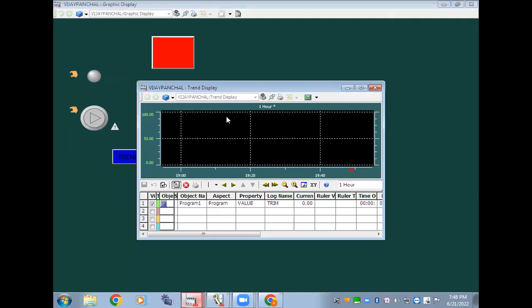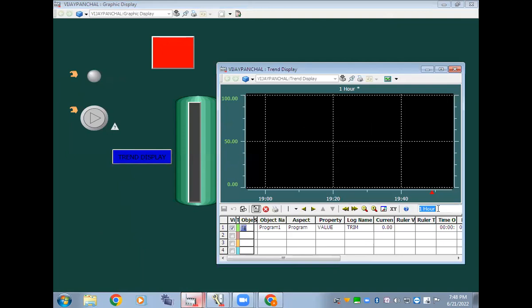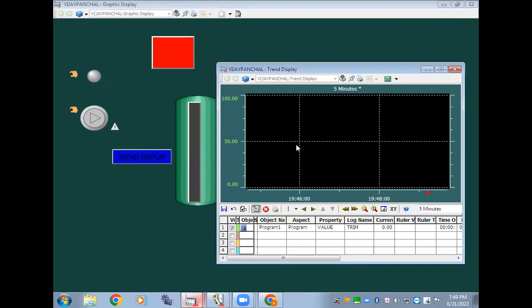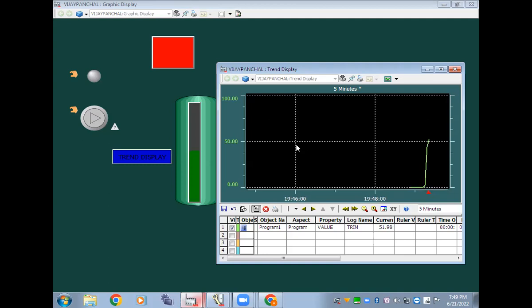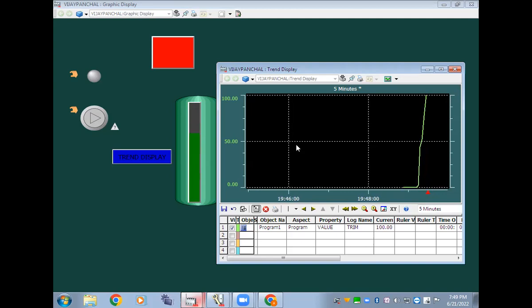Double-tap again. If I click this we'll get this window. Change it to five minutes to show more signal accuracy. You can see — from the field I'm going to vary the regulator, you can see the signal. And if you update, inside the trend display — yes. So this is the way of connecting the variable with your trend display to monitor the value via waveform.